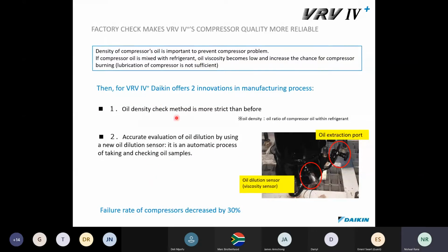So in terms of the density of the compressor's oil, that's also important to prevent compressor problems. Obviously, if you've got a very thick, sludgy oil, you're going to run into issues sooner rather than later. If the compressor oil is also mixed with refrigerant or contaminated, or has gone acidic, the viscosity does become low and increases the chance of the compressor burning out, right? So that's what happens when the lubrication is not sufficient.